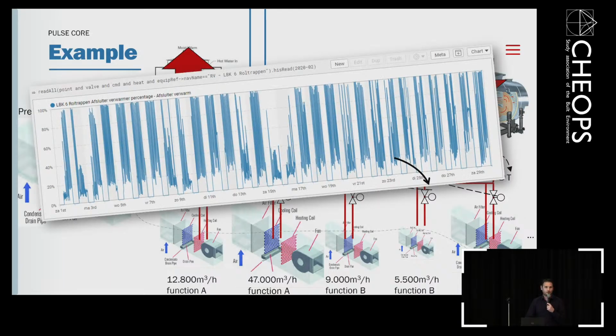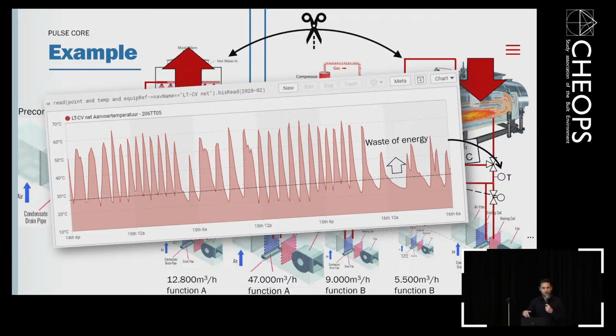And this was what was occurring: you see the valve opening of the small air handling unit rapidly opening and closing. It was a small air handling unit with a system behind it with a very large capacity, so as soon as it opened, it directly closed again. This also meant there was a lot of heat still present inside the system, which then had to be dispatched by the cooling tower. So this design idea was basically flawed.